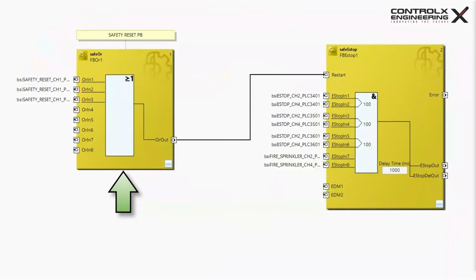On the left side, we have a safe OR function block with inputs tied to 3 normally open momentary push buttons. The output of the function block is tied to the restart input of the safe e-stop function block. The safe e-stop function block has several inputs from various safety inputs. The outputs of one function block can be linked to the input of another simply by connecting them with lines as shown here.